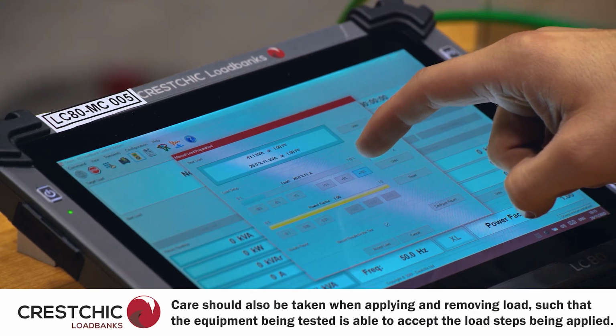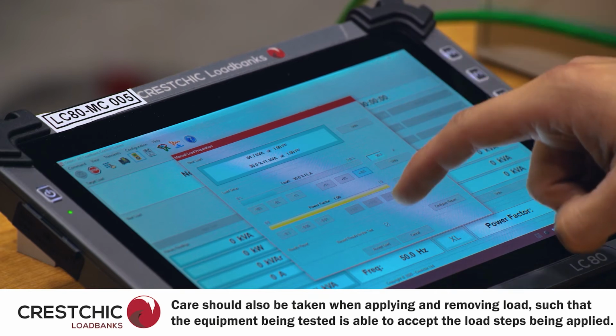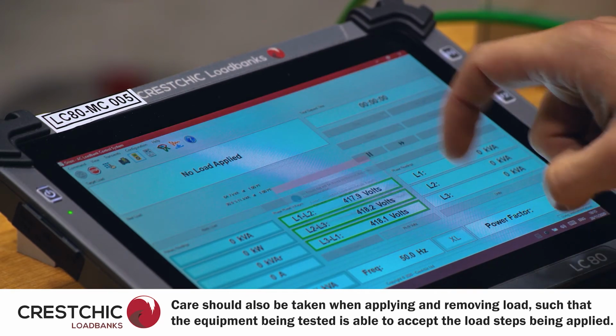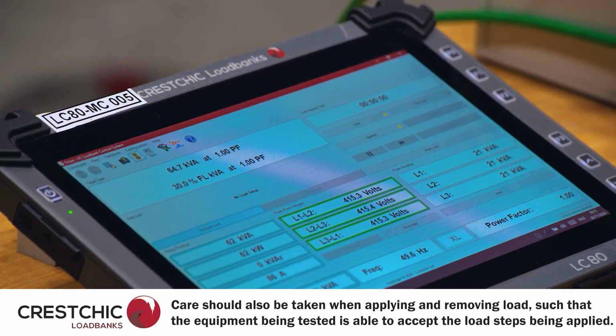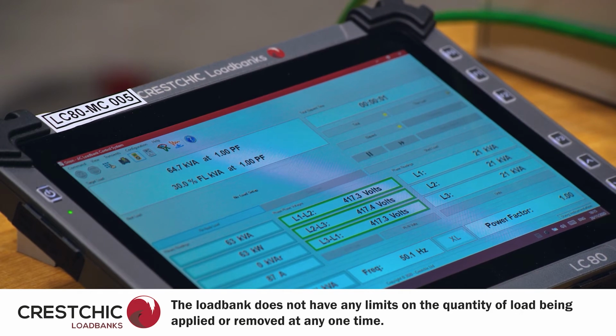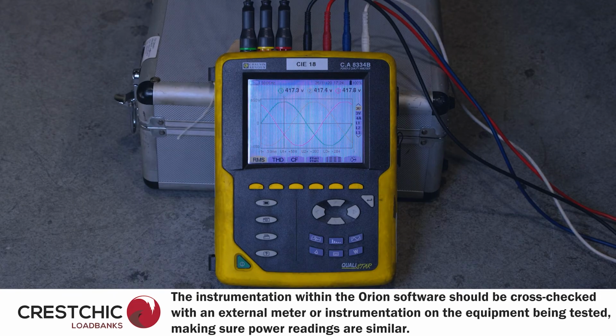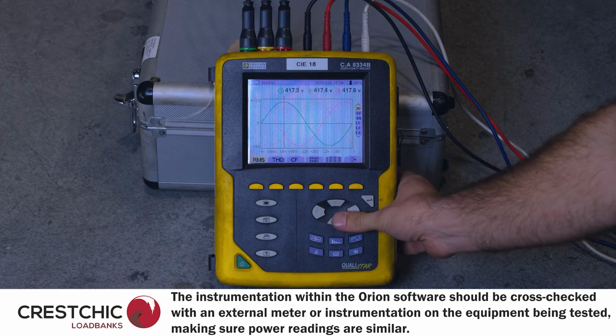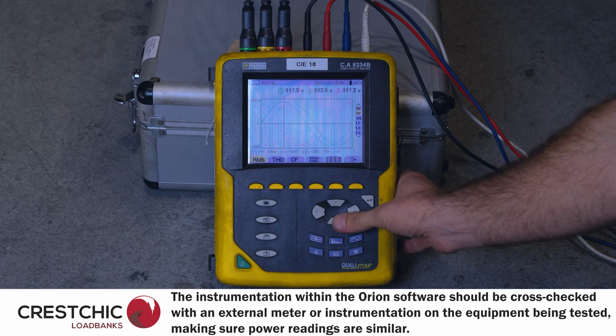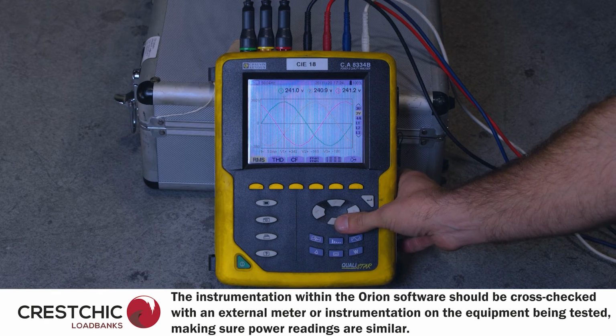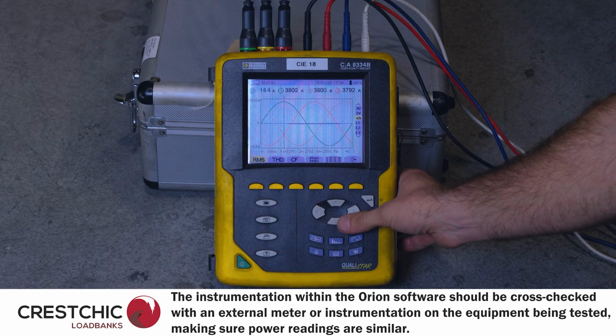Care should also be taken when applying and removing load in that the equipment being tested is able to accept the load steps being applied. The load bank does not have any limits on the quantity of load being applied or removed at any one time. When load is applied, the instrumentation within the Orion software should be cross-checked with an external meter or instrumentation on the equipment being tested, making sure power readings are similar.